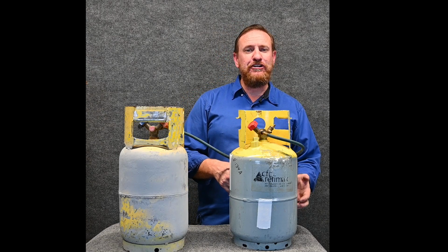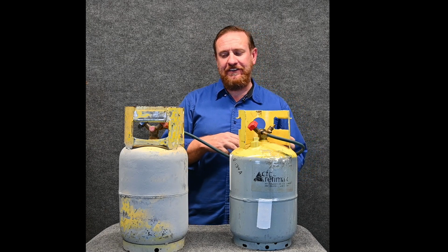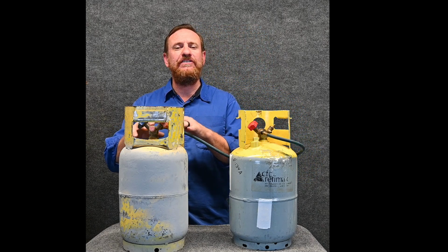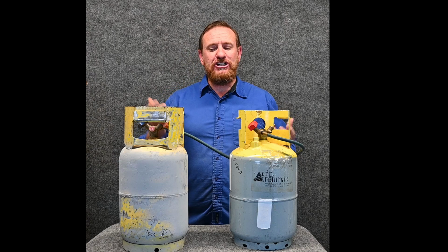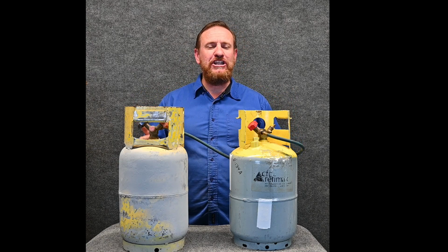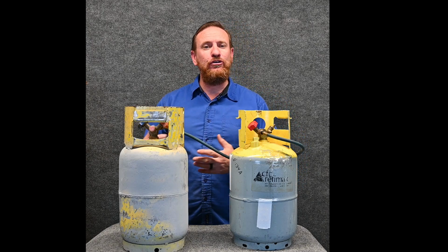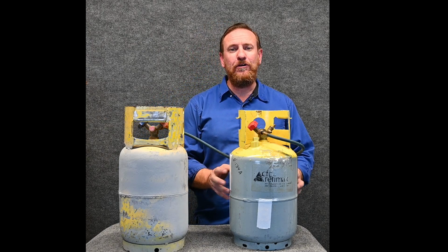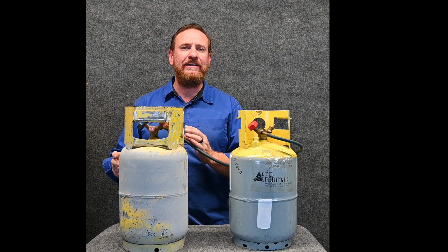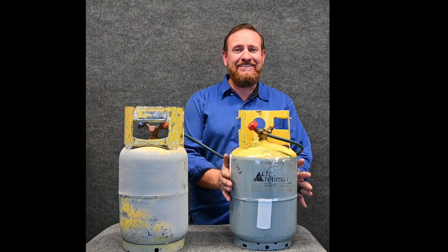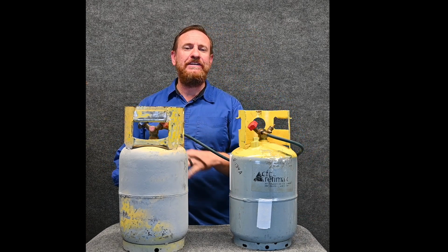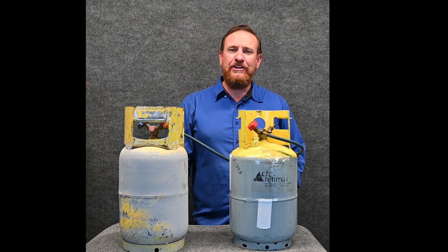So the liquid refrigerant would start to migrate out of this tank and it would start traveling towards this tank. So eventually they would come to an equalization, a point to where they're both the same, but refrigerant likes to migrate to the cooler location. So it's going to leave the warmer area and hang out in the cooler area. So that's one way we can do it. We can heat this tank up and we'll see it migrate over to the one that never changed. But there's yet another way of doing it.